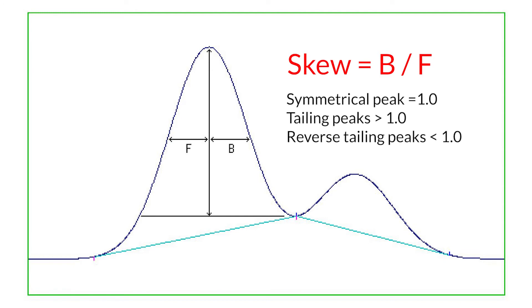Skew values are always positive. A symmetrical peak has a skew of 1.0, and a peak that tails has a skew greater than 1. Rarely, one encounters a peak whose skew is less than 1, indicating reverse tailing.